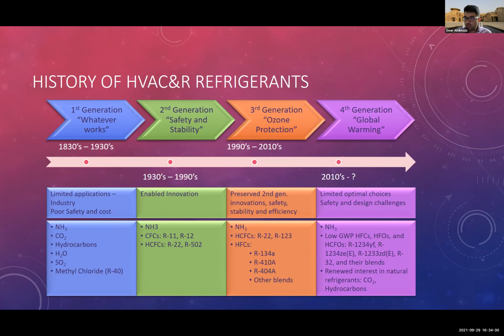Then the Montreal Protocol emerged, and we found that CFCs and HCFCs are harmful for the ozone layer, and we wanted to preserve our ozone. So the ozone protection era moved us to the third generation of refrigerants, between the 1990s and 2010. Again, ammonia was able to continue as an industrial refrigerant of choice, for industrial application and some commercial application. And HCFCs were used as transitional refrigerants, including R22 and R123. And then we saw a burst in the use of hydrofluorocarbons like R134a for refrigeration, air conditioning, and automotive application, R410A for air conditioning application, R404A, as well as other blends.